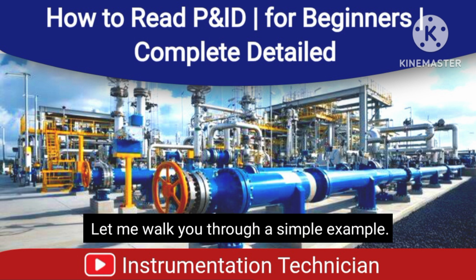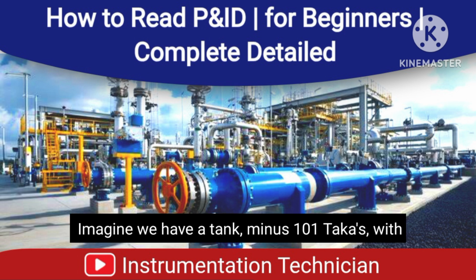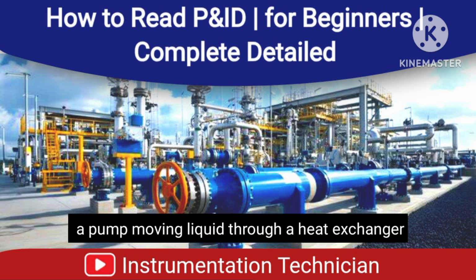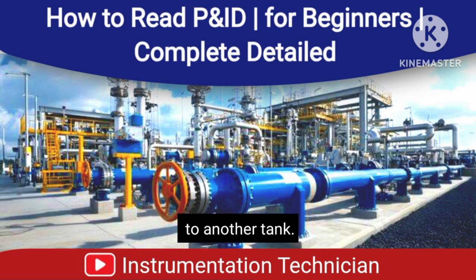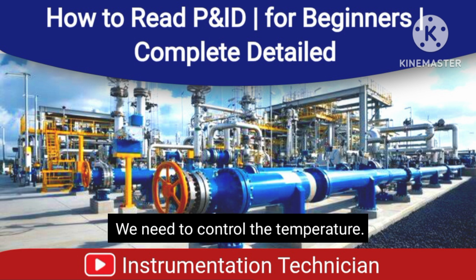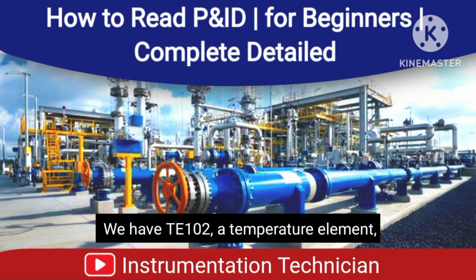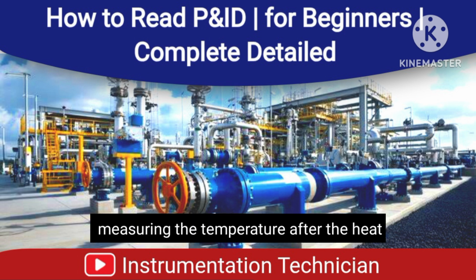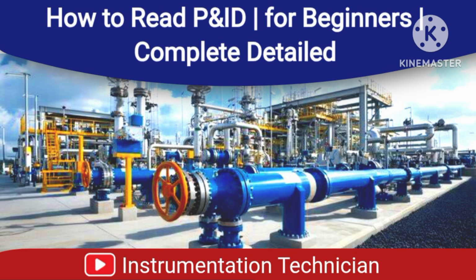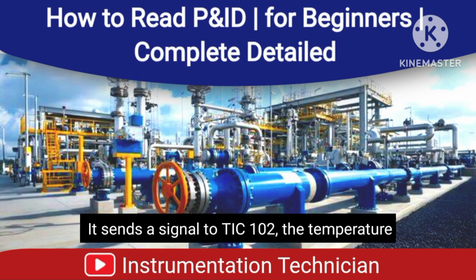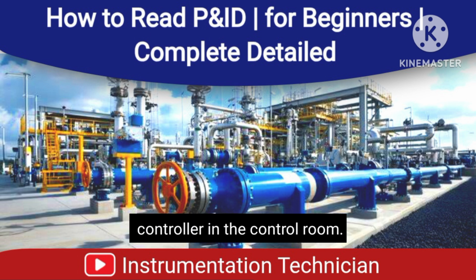Let me walk you through a simple example. Imagine we have a tank, T-101, with a pump moving liquid through a heat exchanger to another tank. We need to control the temperature. We have TE102, a temperature element, measuring the temperature after the heat exchanger. It sends a signal to TIC102, the temperature controller in the control room.